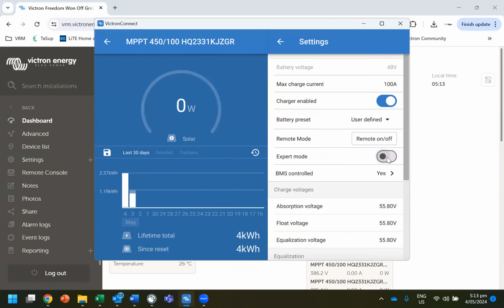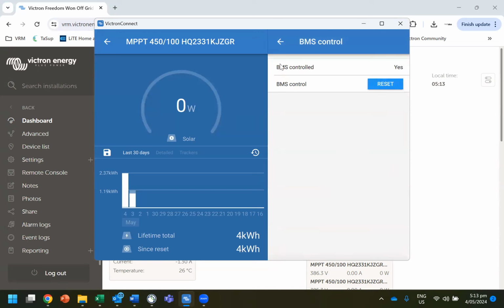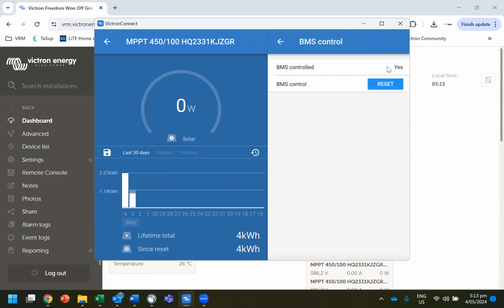And then you may or may not tick expert mode. You really don't need to. Is it BMS controlled? Well, in this case, you don't really have a choice. It's telling you it's BMS controlled and you can reset the BMS control. Now, if I reset this, you watch, I'm going to reset the BMS control. It says no, and it goes straight back to yes. The reason for that is it can see that there's data coming from a BMS, and it's just going to say, I'm BMS controlled. You don't have a choice in disabling that BMS control.